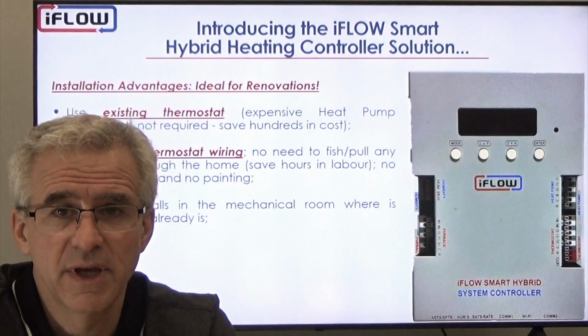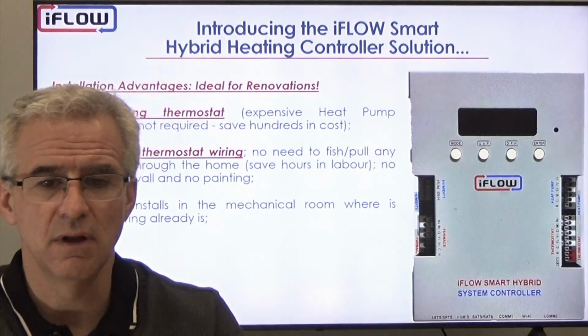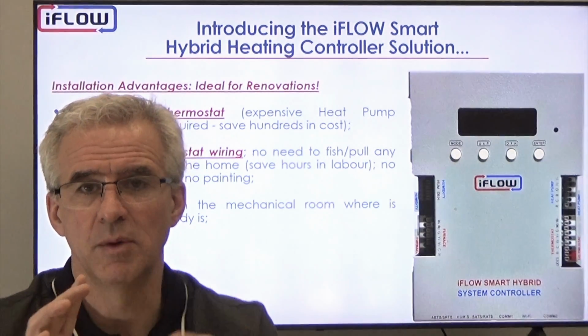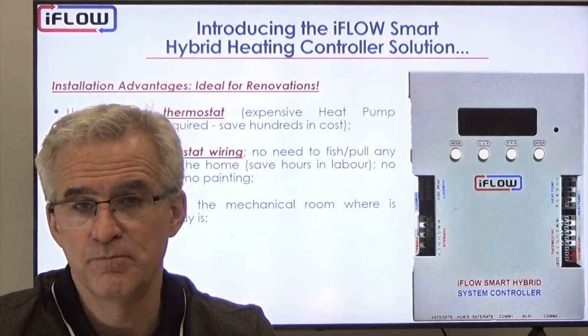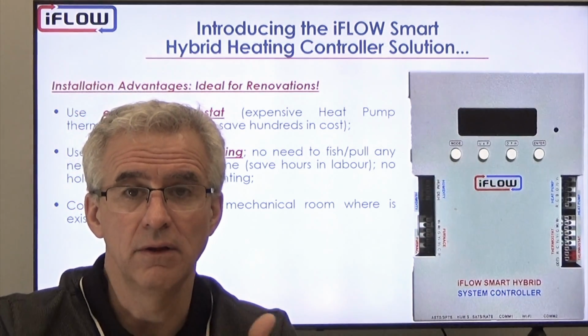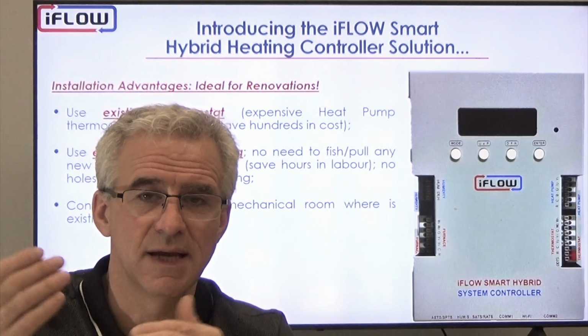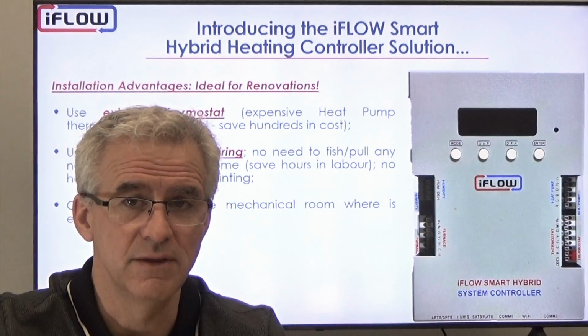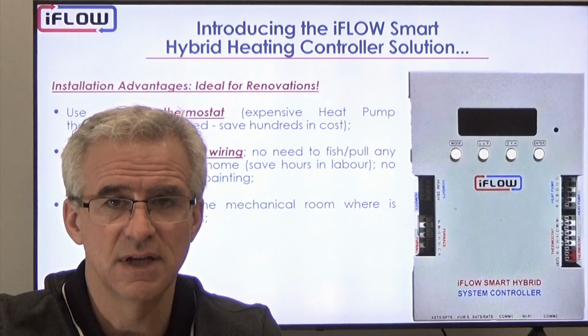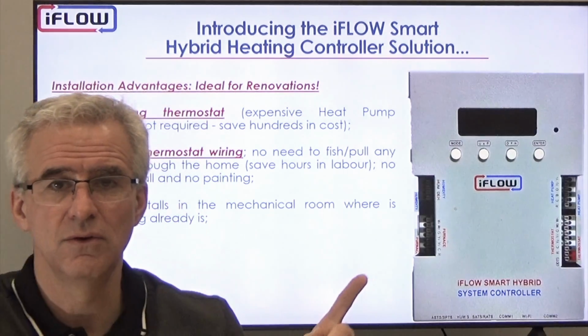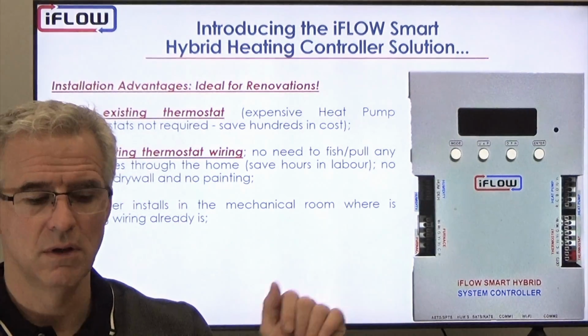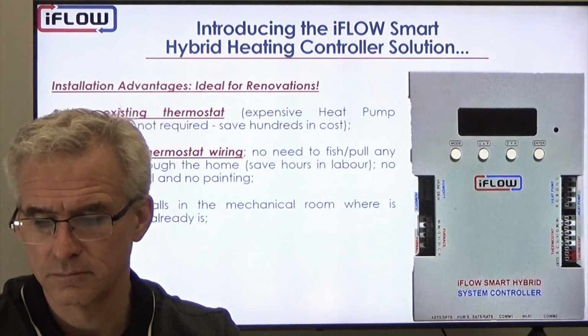The controller's in the mechanical room, so we would install that controller typically on the plenum above the unit. That's where it would be. All the existing wiring from the thermostat down to the furnace is already there. So it's simple, easy: just disconnect it from the furnace, connect it to the right side of the controller, right there.